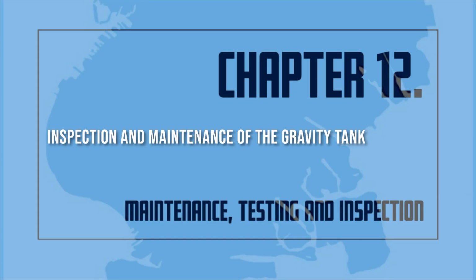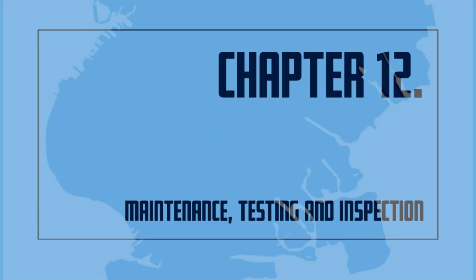It is best if gravity tanks are used only for fire protection and for no other purpose. Tanks used for other purposes need to be refilled more often. The tanks become settling basins for sediment mixed in with the water. This sediment is then drawn into the piping. This may cause the sprinkler system to become clogged and not work properly. The local firehouse should always be notified when a tank cannot be used for any reason.